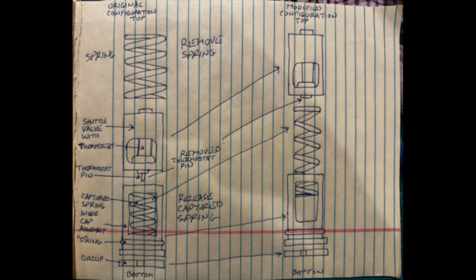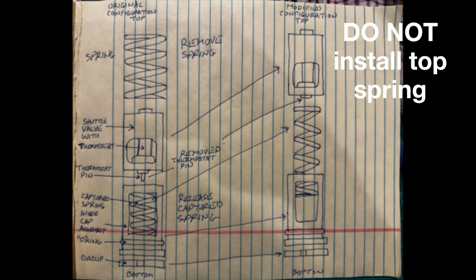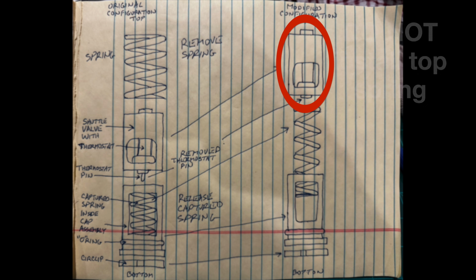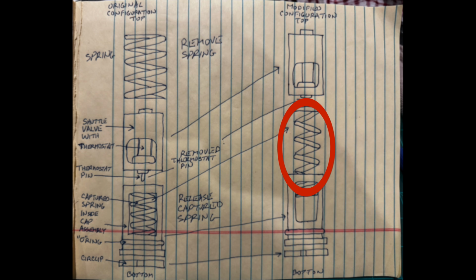To put it back together, you want to leave out the top spring. Put in the shuttle valve with the thermostat minus the pin. Put in the bottom spring. Make sure the O-ring is placed properly. And then put back in the circlip.